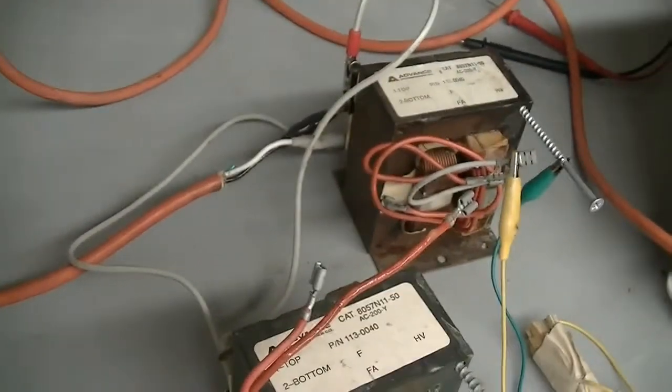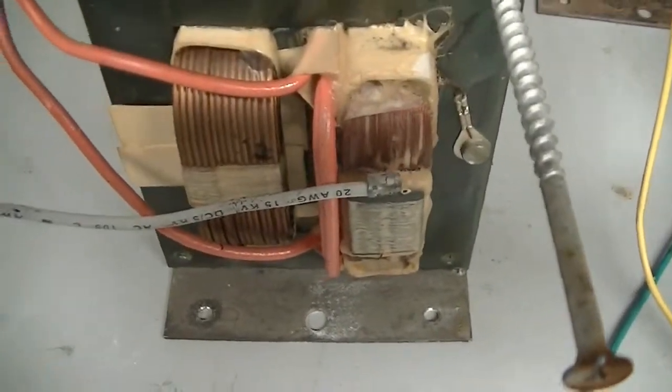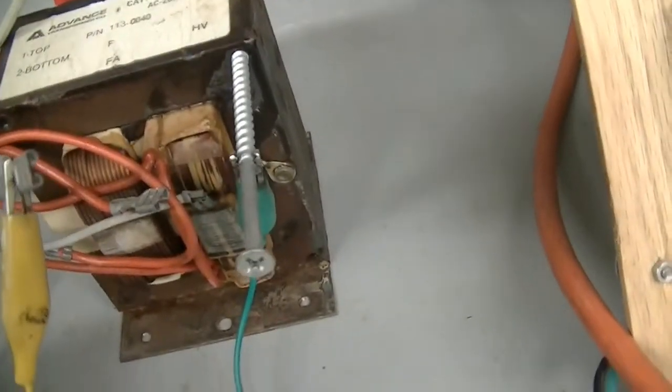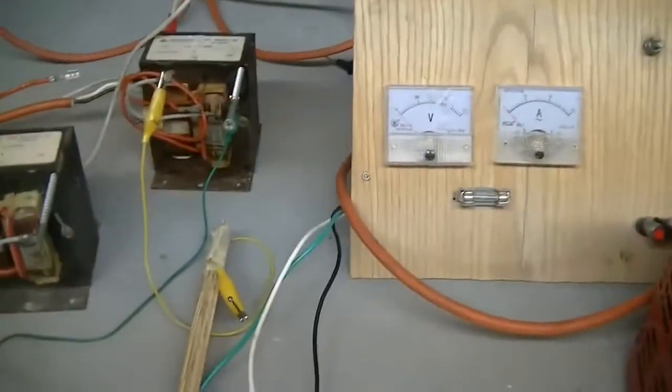Well, both primaries are in parallel. Secondaries are in series. So the input or output of that high voltage coil goes into the ground of that one, and the output of that one goes to the ground of this one, which is for 4,000 volts with 120 volts input.